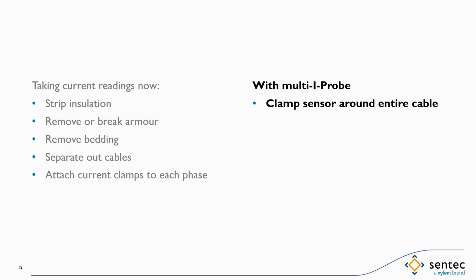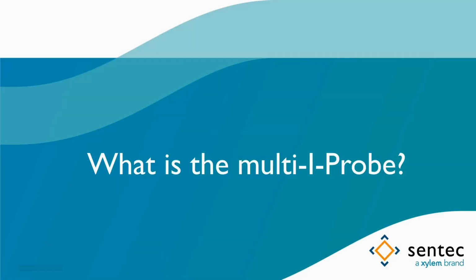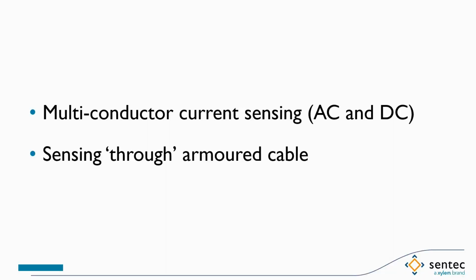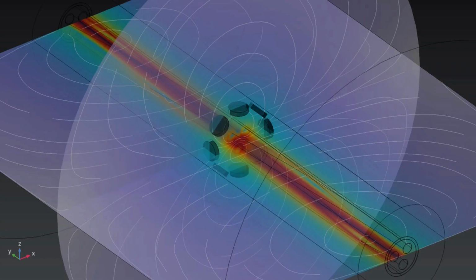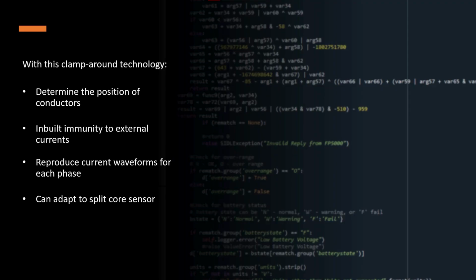around the entire cable. This is a collection of technologies and techniques that can deliver multi-conductor current sensing and sensing through armoured cable. The fundamental arrangement is a ring of magnetic field sensors, either coils or magnetometers. The heart of the technology is the physics-based algorithm. With this clamp-around technology, we can determine the position of the conductors. It has inbuilt immunity to external currents. We can reproduce current waveforms and also measure harmonics.